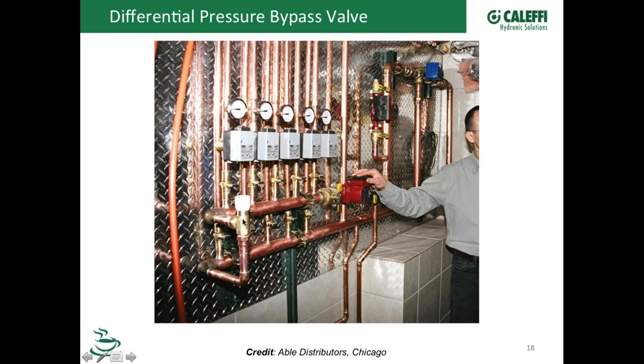If you don't have the chart or you don't know where to set it, just start shutting off valves. And as soon as the first valve shuts off, you should feel a little bit of flow start coming through this pipe here. That's how you know that you're at that threshold where it's going to crack open as soon as the valves start shutting off. And of course, when you get down to all the valves but one open, you'll feel 90% of the flow is going through the bypass valve and back to the pump.